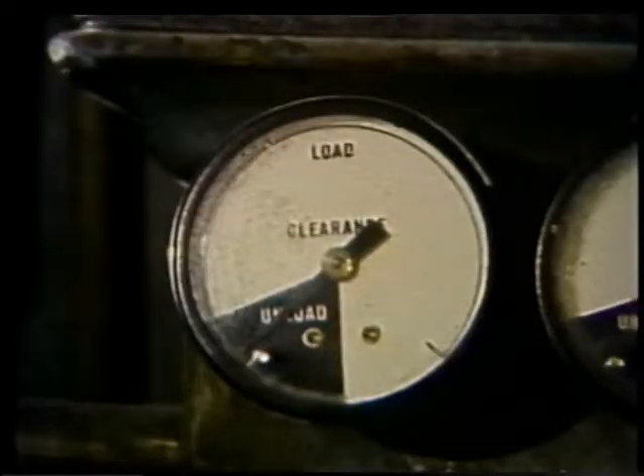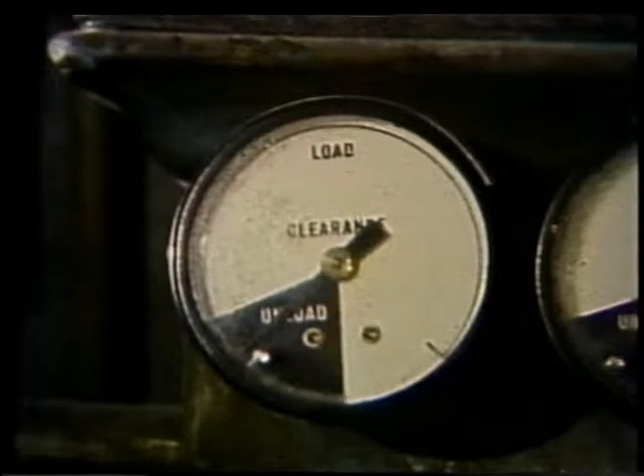For example, suppose you hear a knock. Now, if it comes from the compressor only when the unit is loaded, it's likely to be a valve knock. If the compressor knocks all the time, whether it's loaded or unloaded, it's not a valve. In an unloaded condition, there's no pressure to operate the valves, so the problem's either in the cylinder or in the bearings. Remember, anything that you can find out about the condition of the compressor is to your advantage, so get all of the facts.